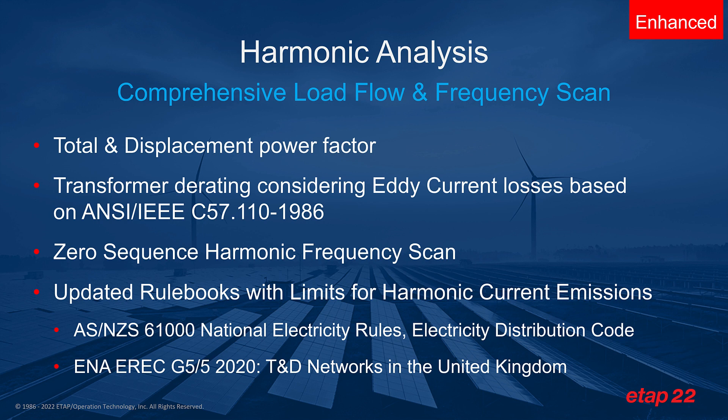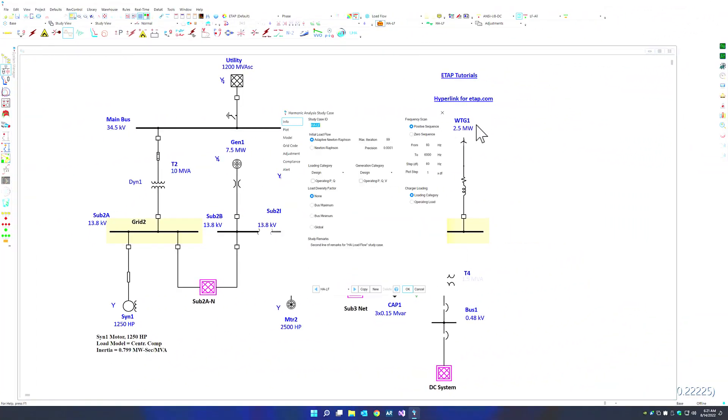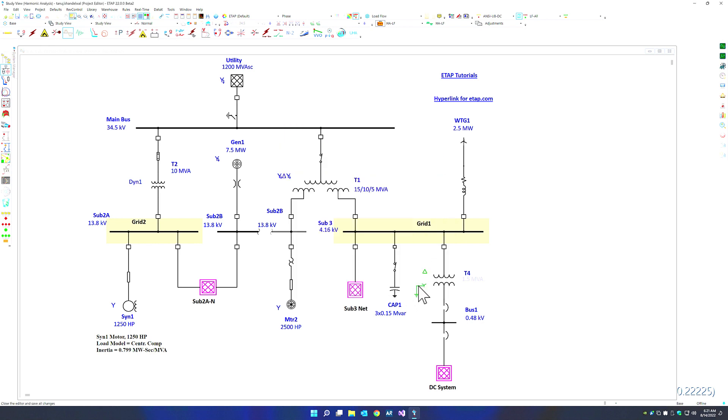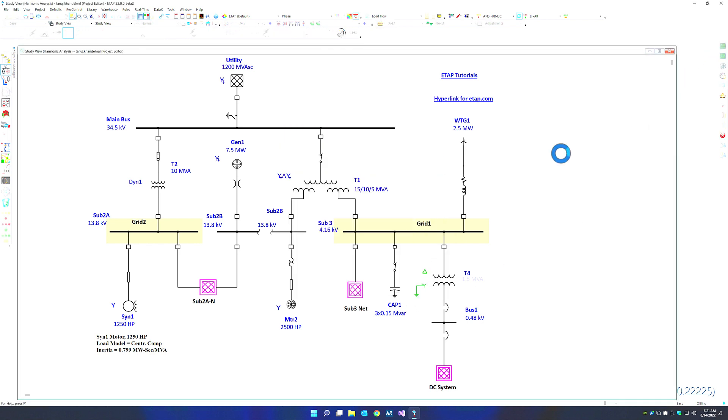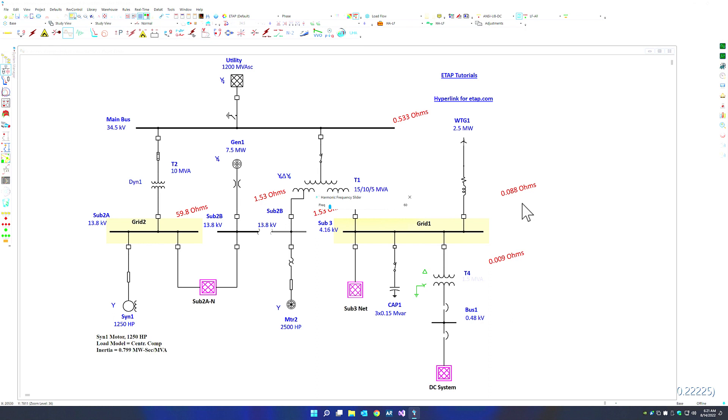So let's see a few of these in action within ETAP. The harmonic analysis zero sequence scan is selected from the study case, so you can choose between the existing positive sequence or switch over to the zero sequence network and run the frequency scan.